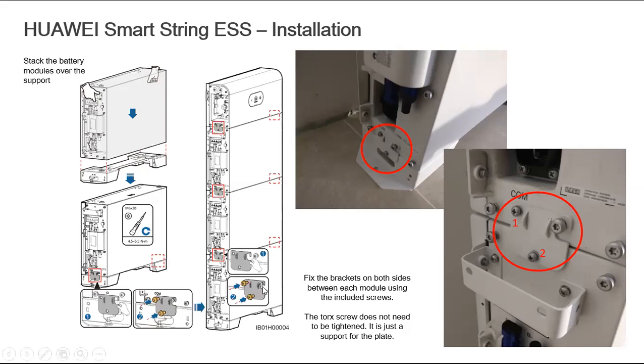And you will see there is another screw which is already tightened there. You don't need to move or tighten that screw, because it is there to support the expansion plates for the LUNA battery system. On the right side of the screen, number 1 and number 2 are the two screws available in the battery box, and the other one is already fixed there. So just tighten screw number 1 and screw number 2, and do the same on both sides of the battery up to the power control module to make the installation safe.